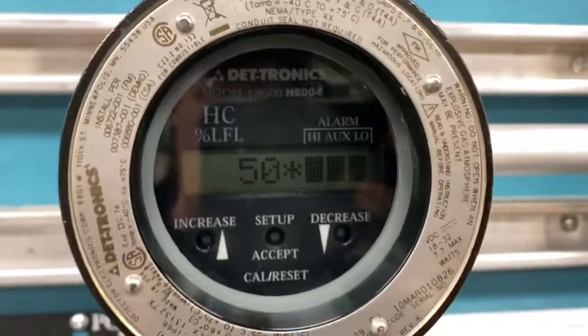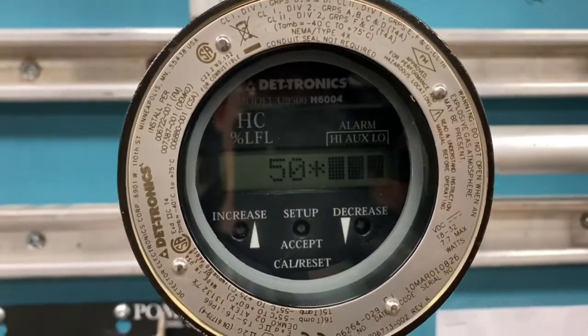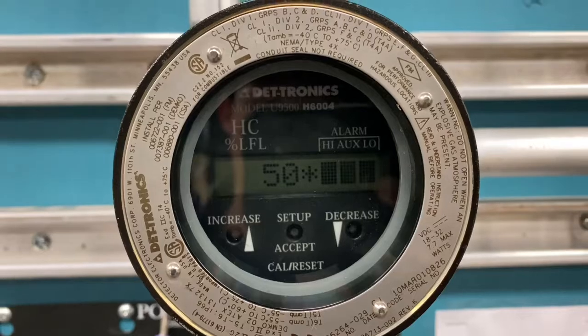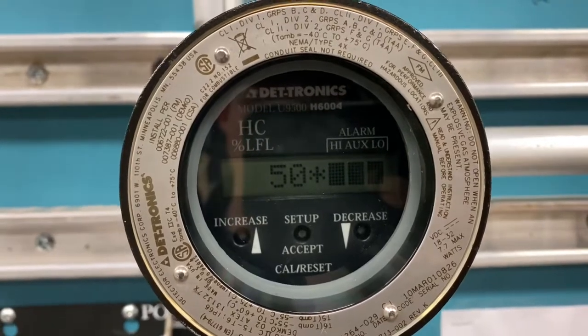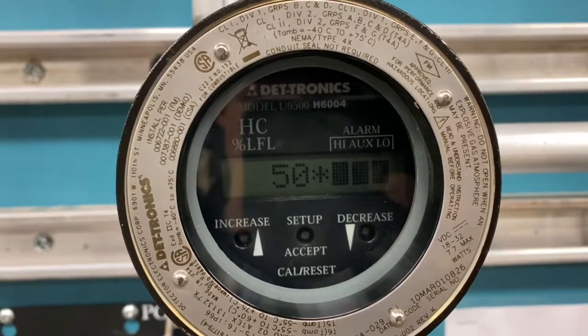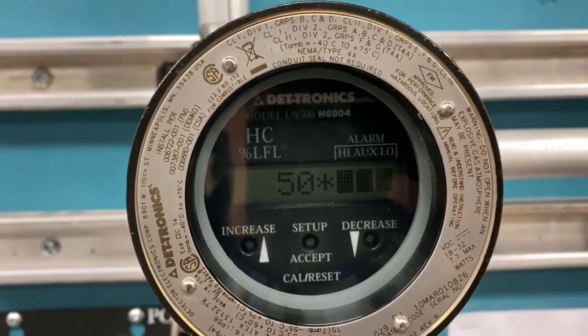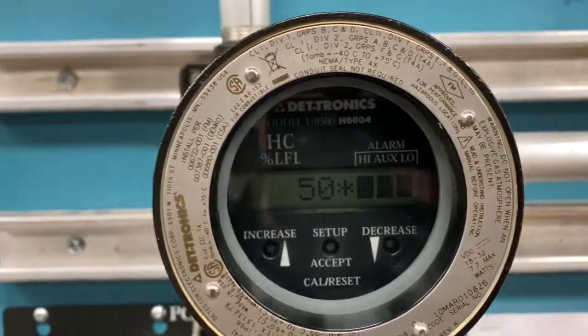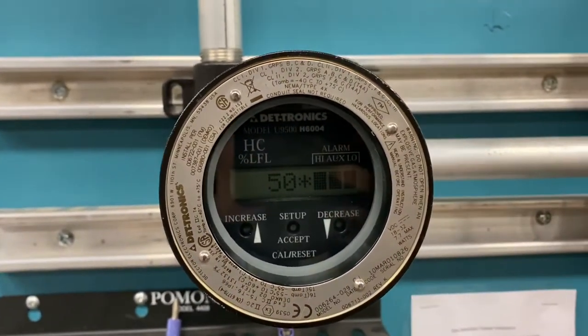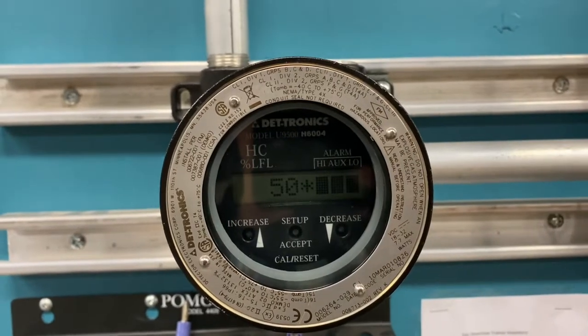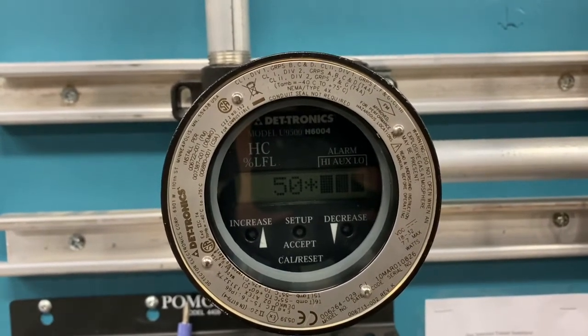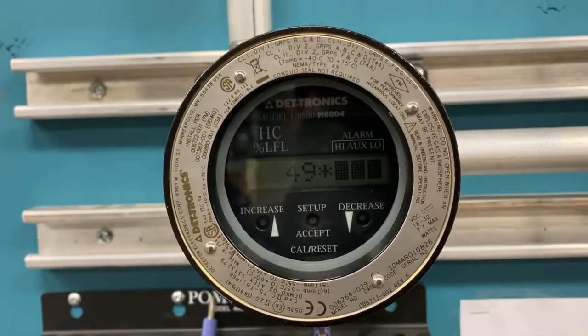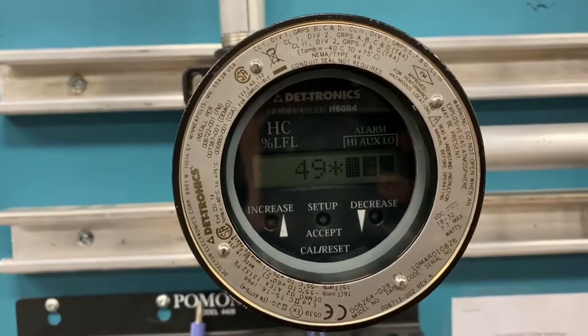There, we're pretty close. And look at that, the sensor hasn't been calibrated in probably about a year, and it was quick to react, and it's stable at 50%. So it won't even need a calibration. Comparing this to the Millennium 2, which drifted quite a bit over the year, the infrared system here looks like the calibration holds pretty good.